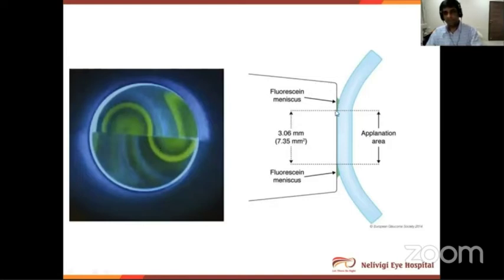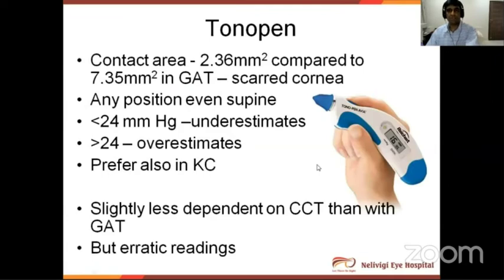So when you applanate, suppose this is the applanation prism of the applanation tonometer. When it comes in contact with the cornea, it applanates this much area. The corner between the prism and the applanated cornea causes the fluorescein dye to remain like that. And this is what we see as these mires over here. So when you have a specific amount of weight which presses on the cornea, that is how the shape of these rings would change and give us the intraocular pressure.